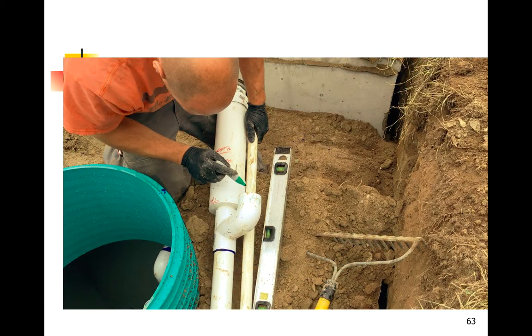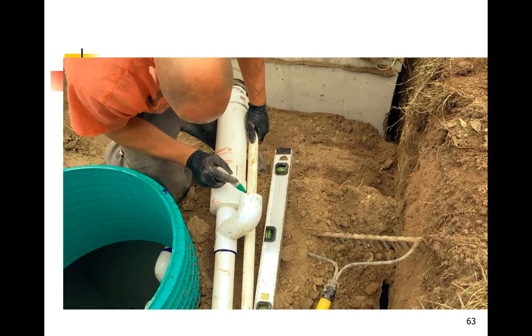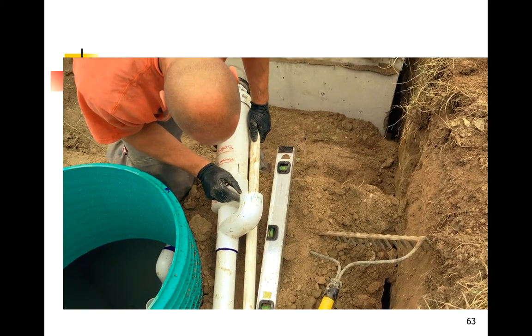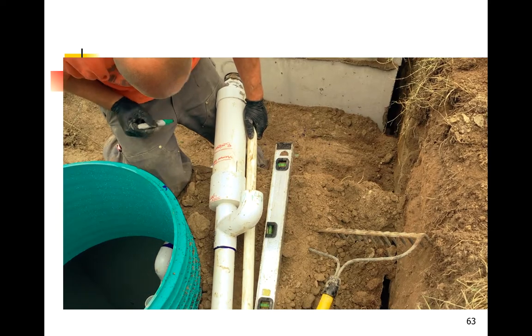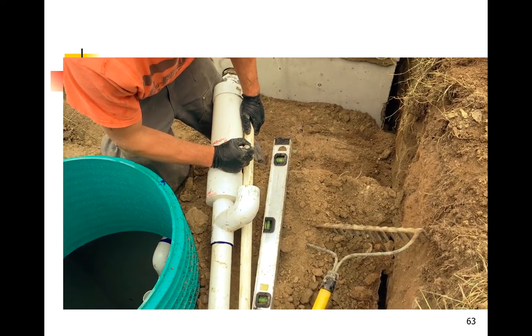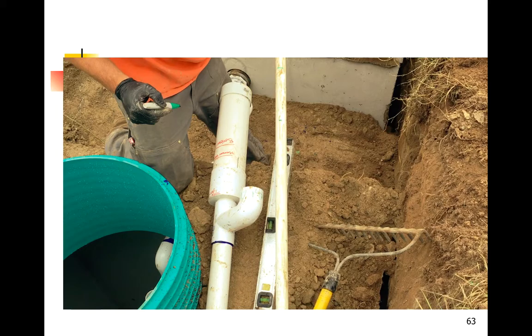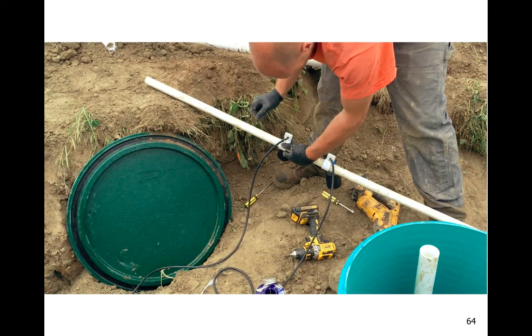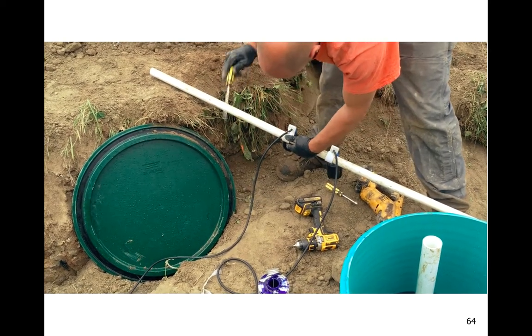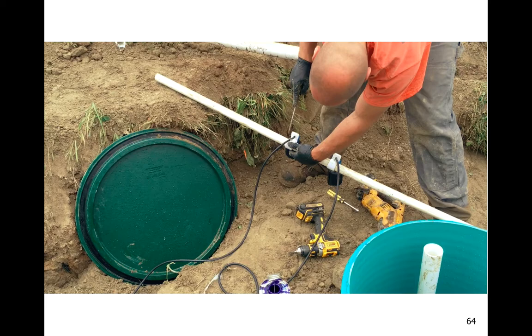We're going to line up one end of that 1-inch pipe to the top of the splitter valve, the handle itself, and then we're going to mark where the floats go. The 4-inch shroud is marked with markings for top float and bottom float. So just make a mark on your 1-inch pipe. And then the floats that come with the system are already attached to a float clip, and the screw itself is going to be fixed at those marks.